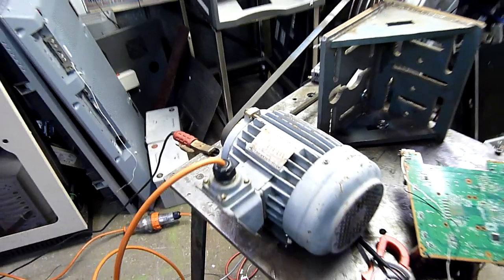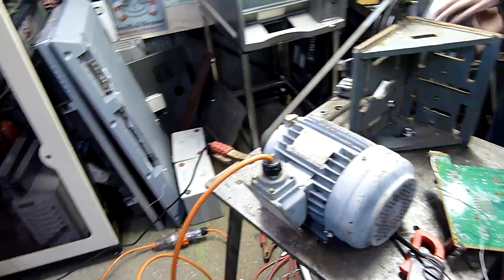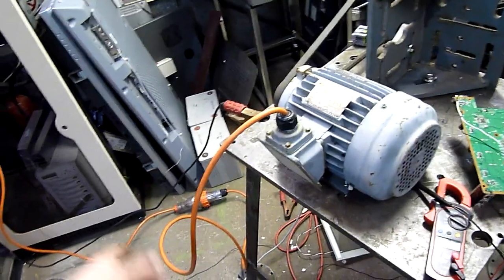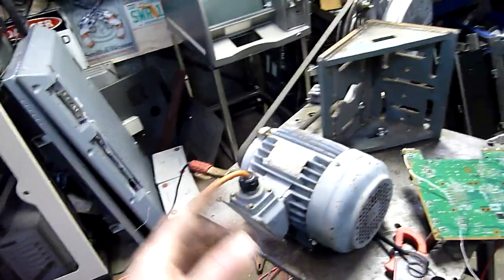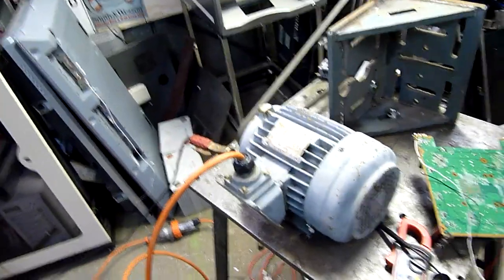That motor went under some insane stress. Still stone cold. The windings themselves would be a little bit warmer. That's called a stall essentially. The frequency going through the windings exceeds the speed that the rotor can do, and the rotor starts to just lose momentum, slow down and stall. It's like an aircraft without flaps.